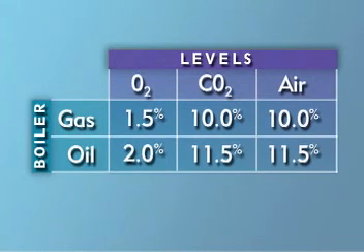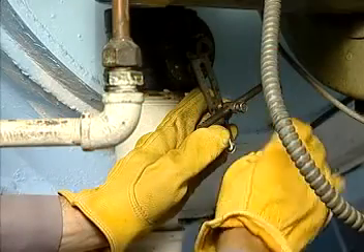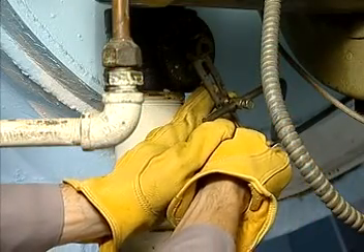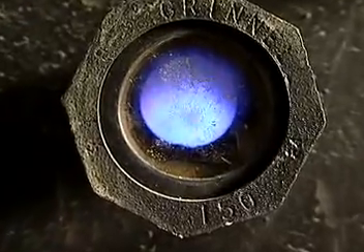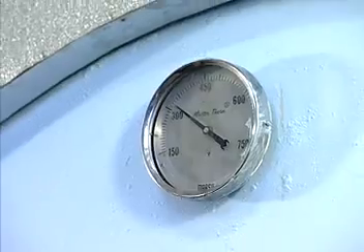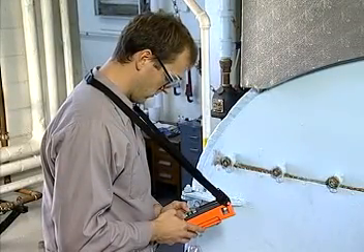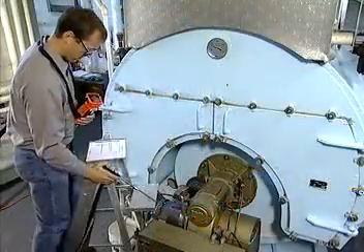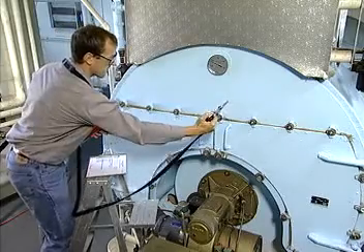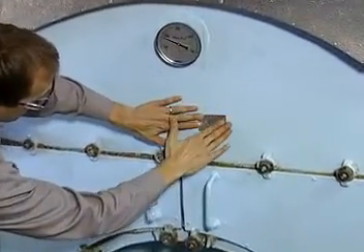On fuel oil-fired boilers utilizing number 2 fuel, typical excess oxygen levels should be maintained at approximately 2% with a corresponding carbon dioxide level of 11.5%. After the air-fuel adjustments have been made, record the color and condition of the boiler flame, as well as the stack temperature on the log sheet. Repeat this process for medium and low-fire operation. Wait several minutes between each test to allow the boiler to stabilize. Seal the test hole to prevent any leaking of combustion gases into the boiler room.